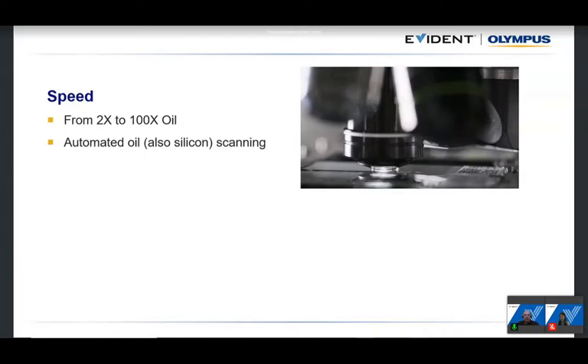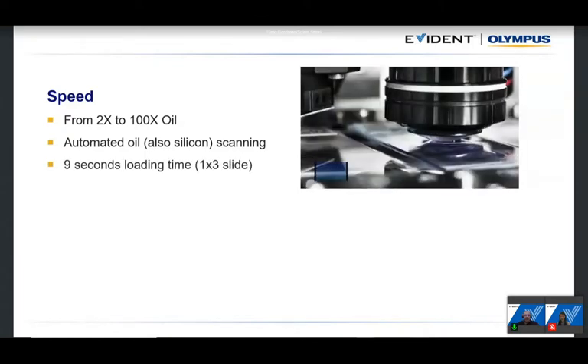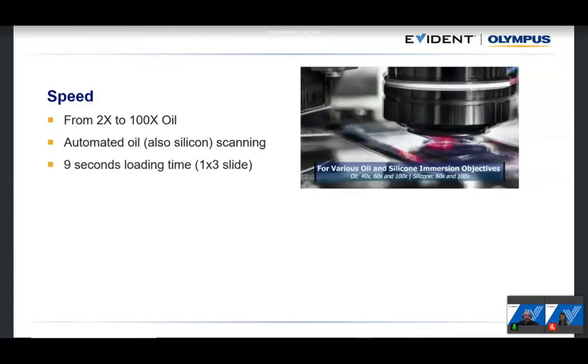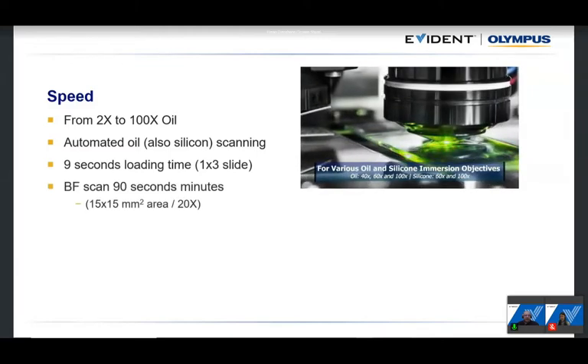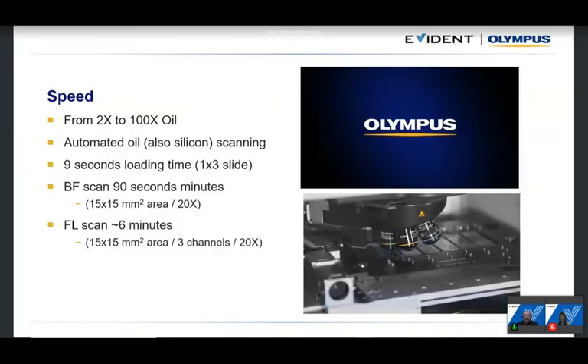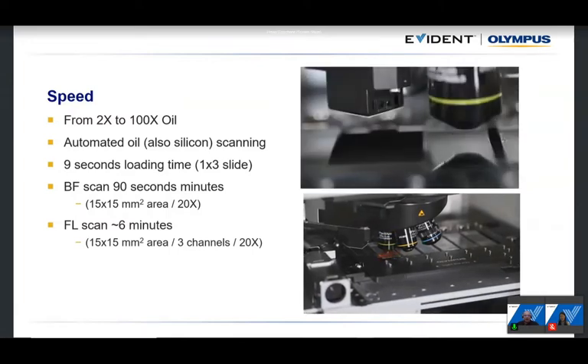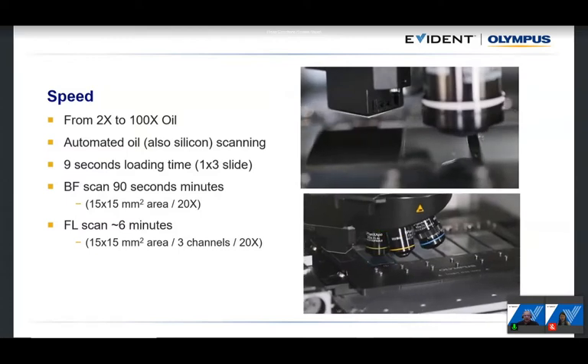We have very fast loading times — each slide can be loaded in about nine seconds. Brightfield scans take about 90 seconds for a standard 15 by 15 mm area at 20x. Fluorescence is also very fast: the same area with three channels at 20x single layer can be acquired in six minutes, which is quite fast.